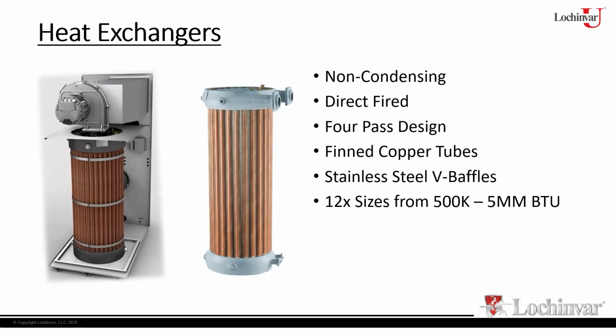Once all the tubes are rolled into position, then at that point we will do a hydrostatic water pressure test of 1.5 times. Again, all these heat exchangers are approved for 160 pounds of pressure. So that means they're going to be tested to 240. If there is a leak at 240 PSI, we're going to find it.